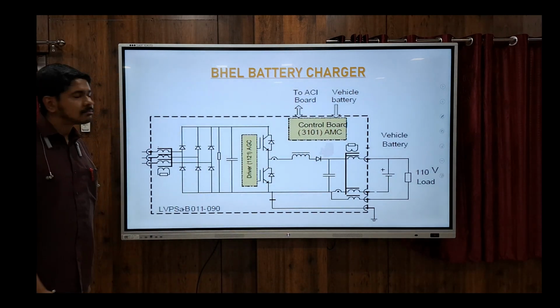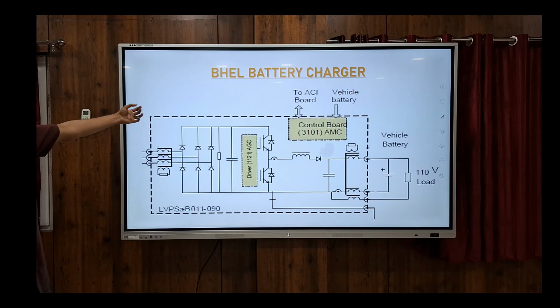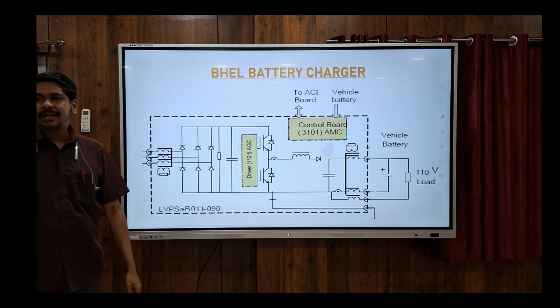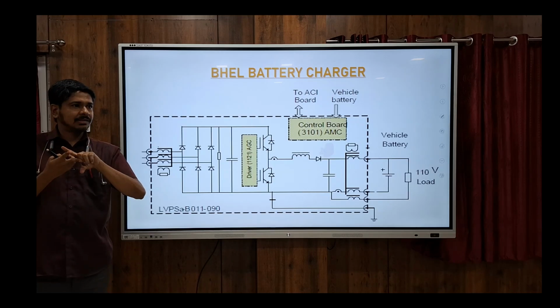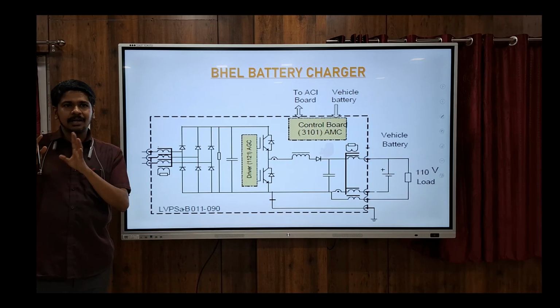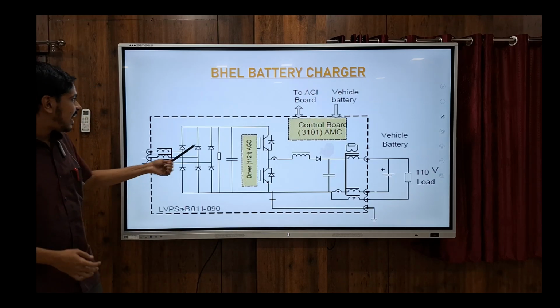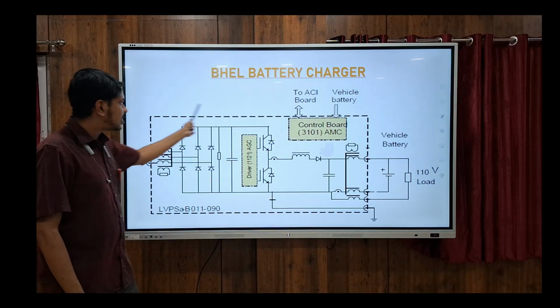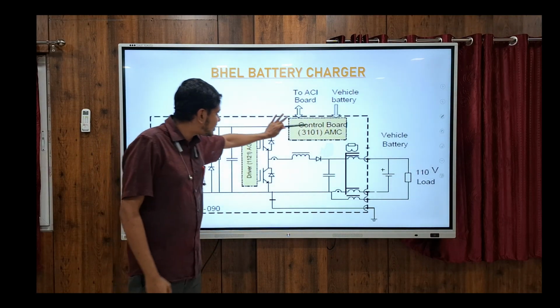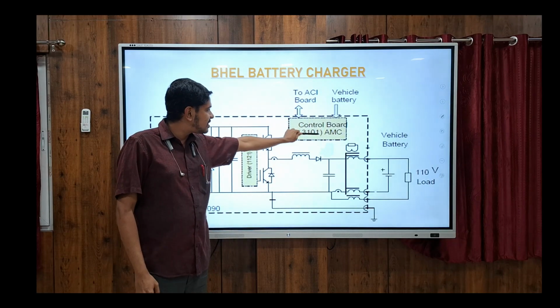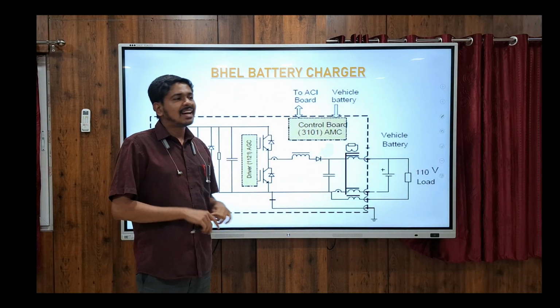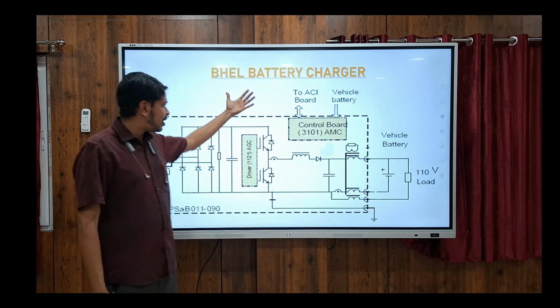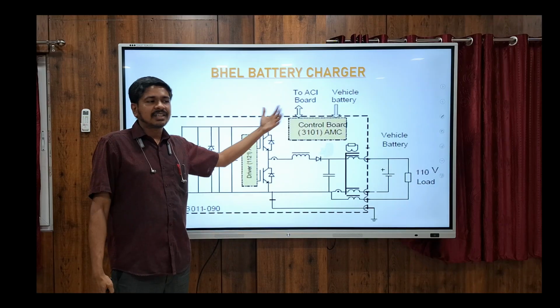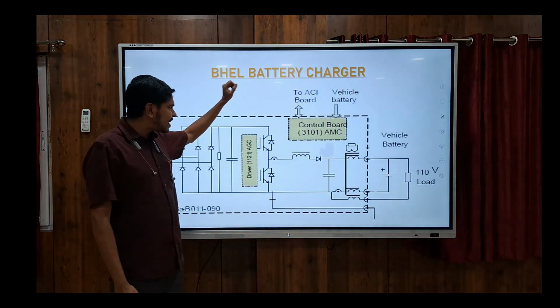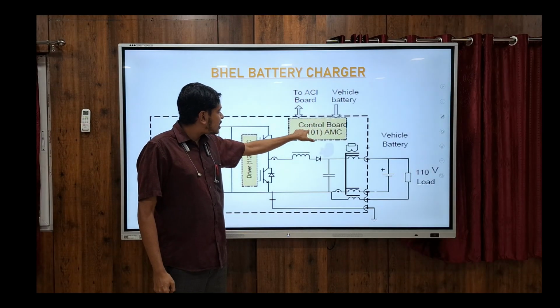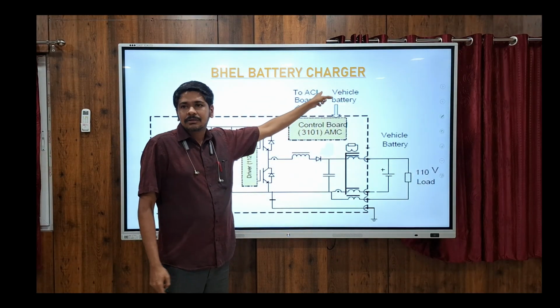This is the BHEL battery charger. This configuration is slightly different, let me explain. Mainly it has two cards, the ACI card and the AMC card. The AMC card monitors all the functions of the battery charger module, and the controller of this AMC card is the ACI card. That card decides in which mode it should work, whether it is communicating properly or not, whether it is working properly or not. The AMC card has to communicate to that master card, the ACI card.